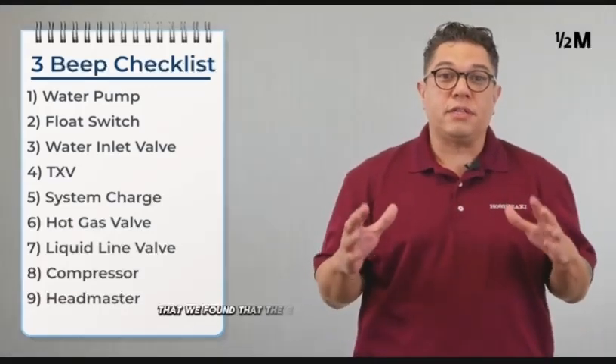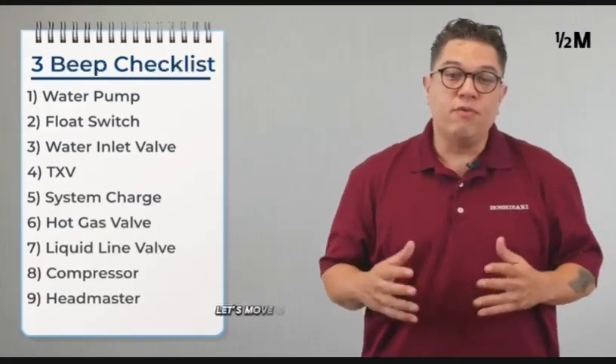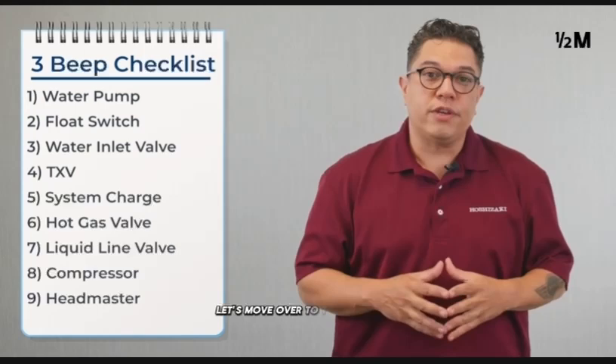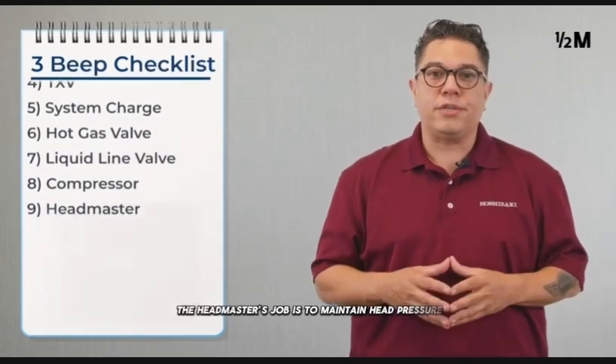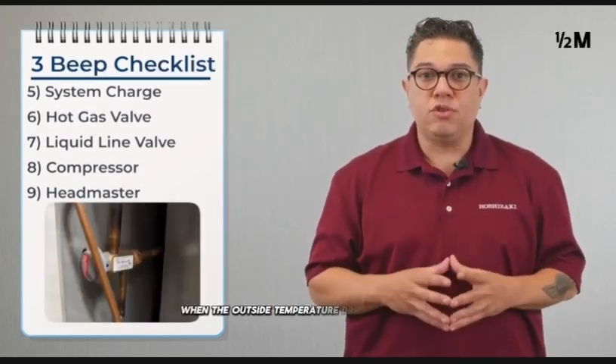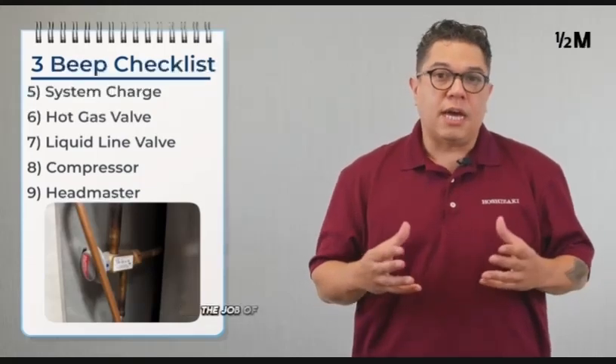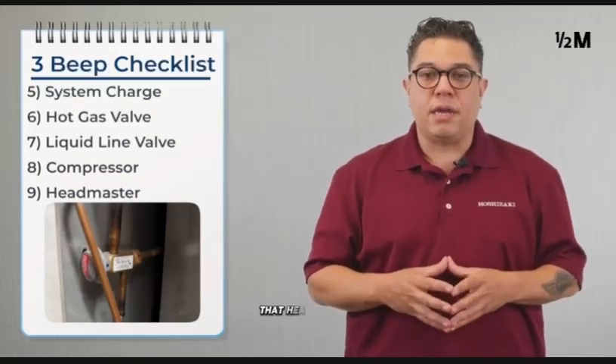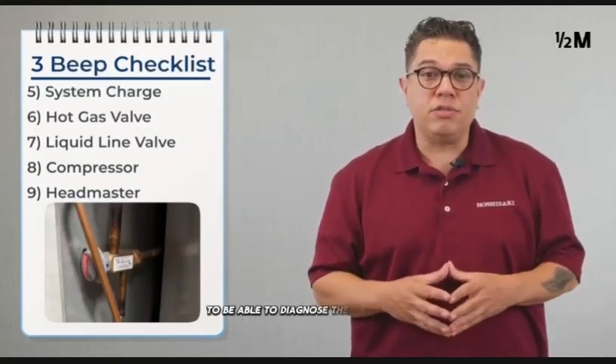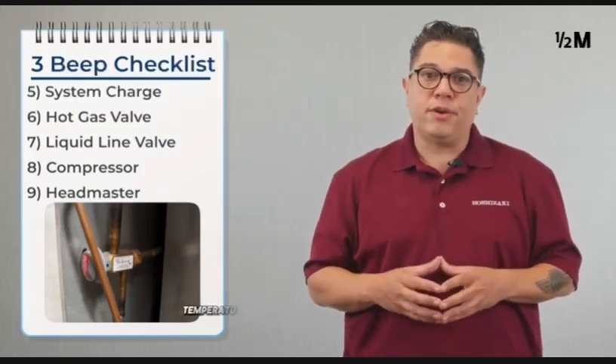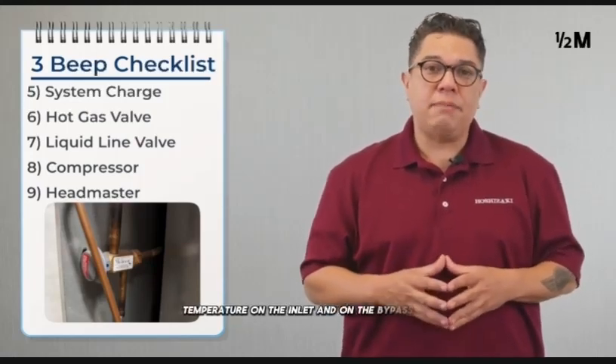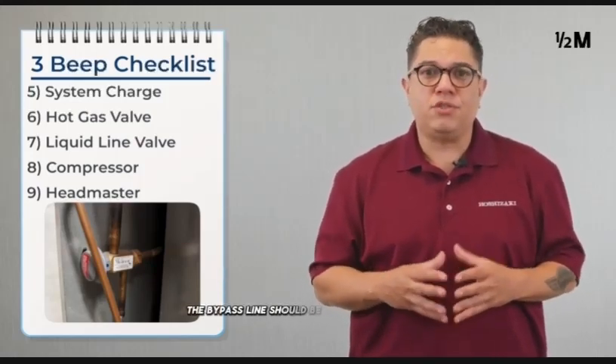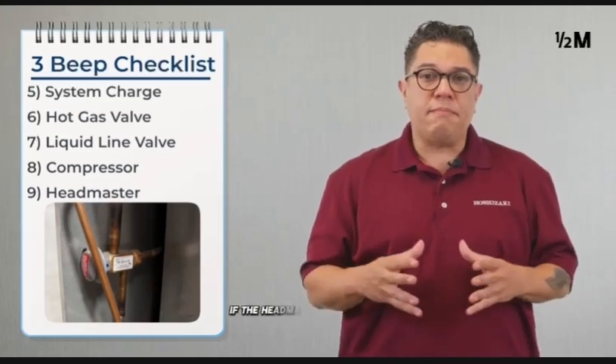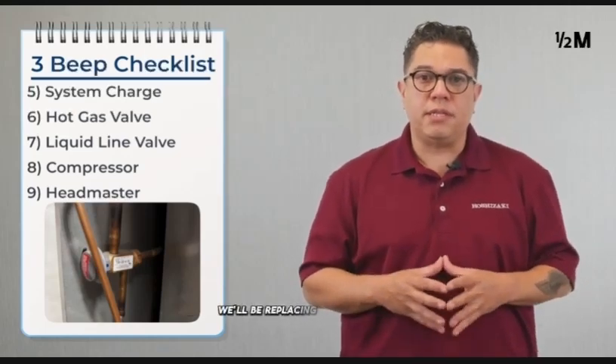Now that we found that the compressor is working properly, let's move over to the headmaster. The headmaster's job is to maintain head pressure. When the outside temperature drops drastically, the job of the headmaster is to maintain that head pressure. To be able to diagnose the headmaster, we're going to take a temperature on the inlet and on the bypass line. The bypass line should be ambient temperature. If the headmaster is bypassing, we'll be replacing the headmaster.